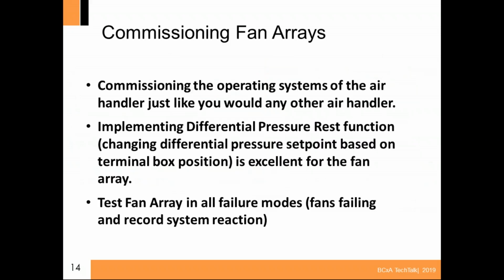How I commission them is I look at the air handler, and I commission the air handler like I would commission any other air handler, all the way through chilled water valves, chasing temperatures and stuff like that. In a fan wall, I want to implement a differential pressure reset function. I want to change the differential pressure based upon where the terminal box is positioned. And that way I can actually dial back and take away the fat that the engineer built into it, because I don't want to put as much energy into moving that air and maintaining static pressure that I don't need to. And I think my client doesn't want that either.